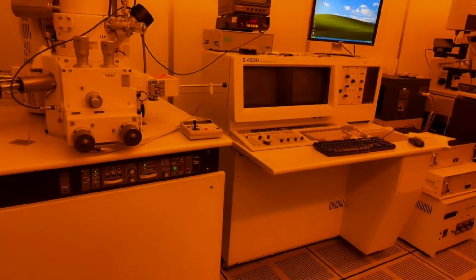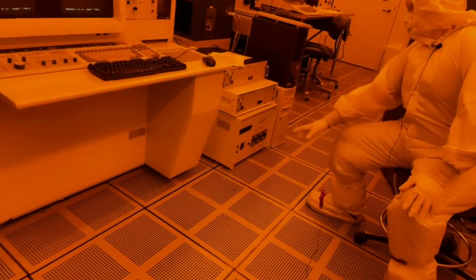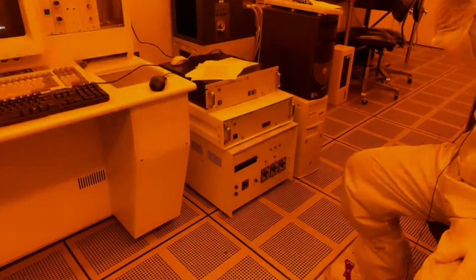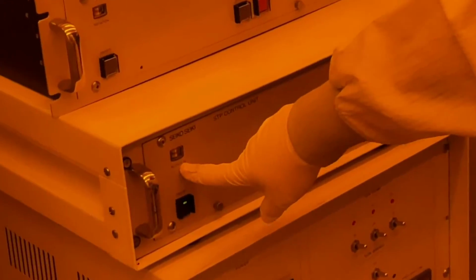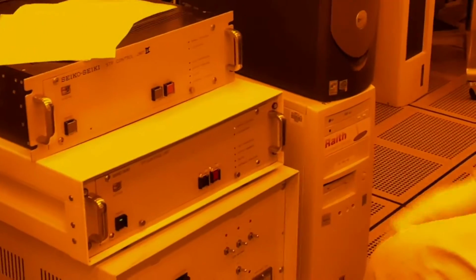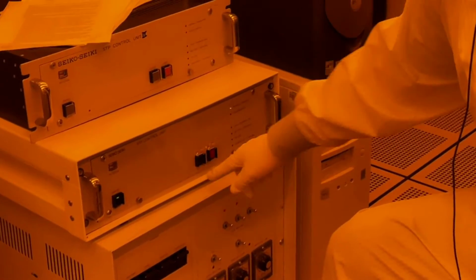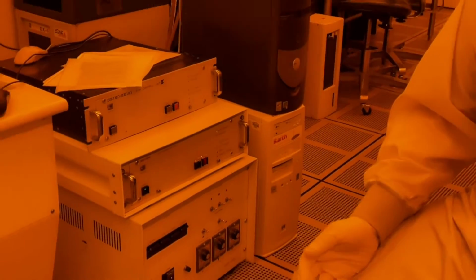Next, we can go over to the panels for the vacuum system. Over here, we have a STP control unit for the turbo pump. It has a gauge right here indicating the rotation speed. As you can see, the needle here is now in the green, indicating that it's in normal rotation speed. We have a main power, and then start and stop to the motor. Then we have indicators of the state. So right now, it's running in a normal operation state. If it's off, say, for example, for some reason the pump gets turned off or it gets tripped, you'll start it, go to acceleration, and then to normal operation. It also has all these indications to diagnose issues with the system.